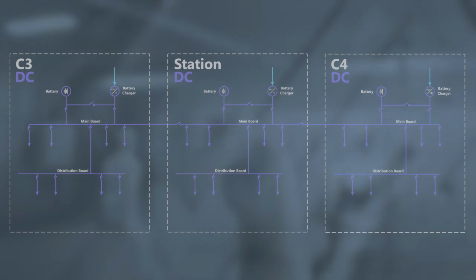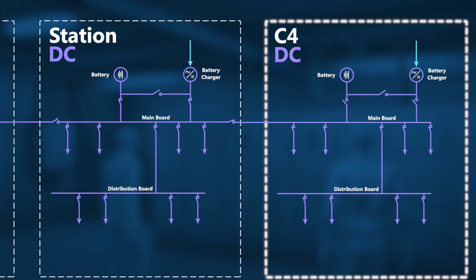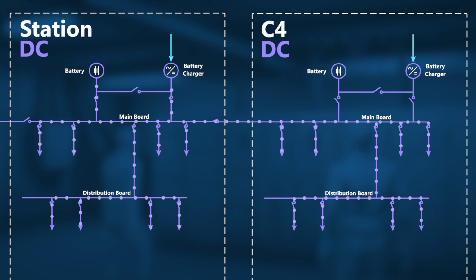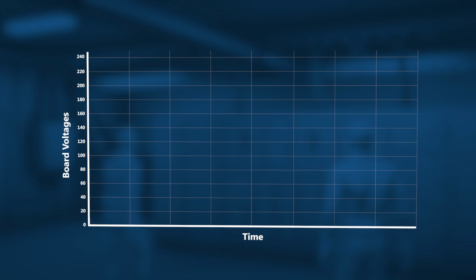But what had actually happened when the interconnector was opened? How did this lead to the loss of DC? And why was the AC system lost as well? First, let's look at the voltage level in the C4 DC system. Up until the interconnector was opened, this voltage was being supplied from station. A voltage level of between 190 and 242 volts is required for the system to operate as designed. So, when the interconnector was opened, the system required the C4 battery charger to maintain the voltage at this level. This did not occur. When the interconnector was opened, the voltage in the DC system instantly collapsed.